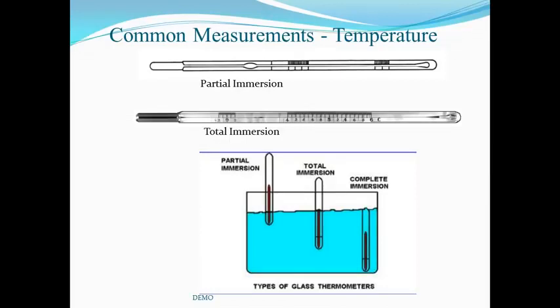A highly used temperature measuring device is the glass thermometer. They typically come in three different types: a partial immersion, total immersion, and complete immersion model. The application to liquid measurement must be understood to arrive at the best uncertainties for each type. The partial immersion thermometer has an etched line just above the lower expansion chamber to indicate the depth of immersion. A total immersion type depends on the skill of the operator to immerse only the column of mercury or indicating fluid to arrive at a stabilized point.